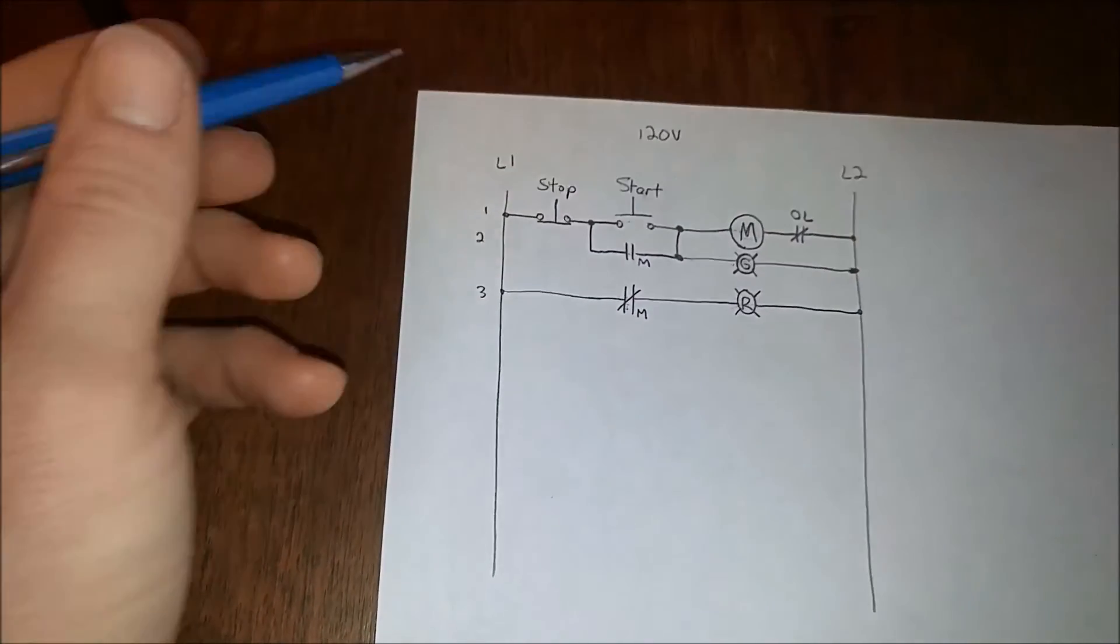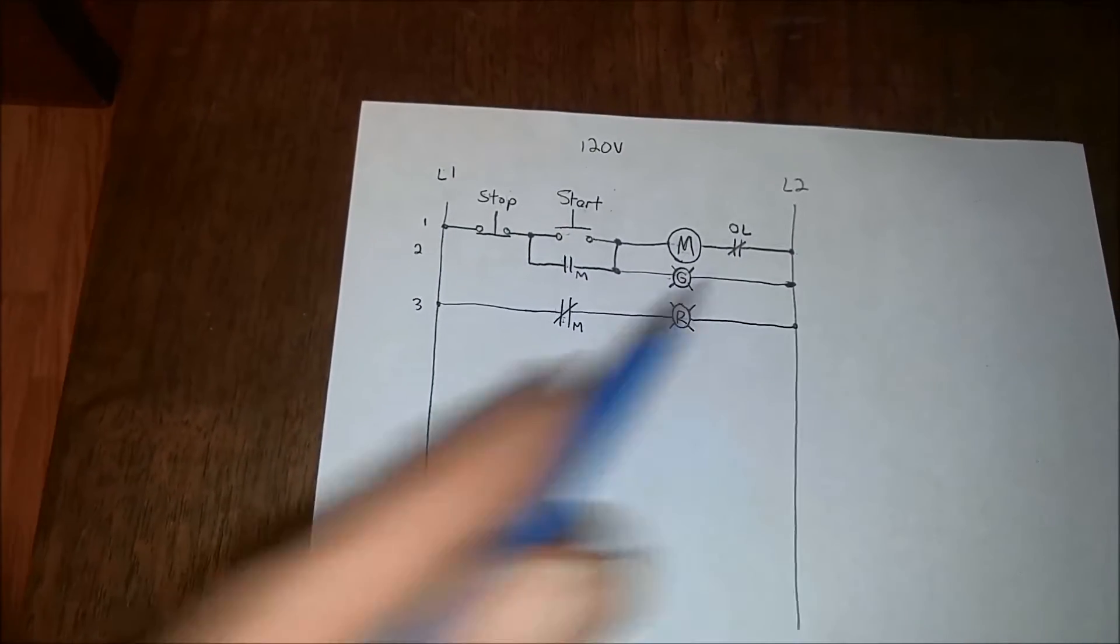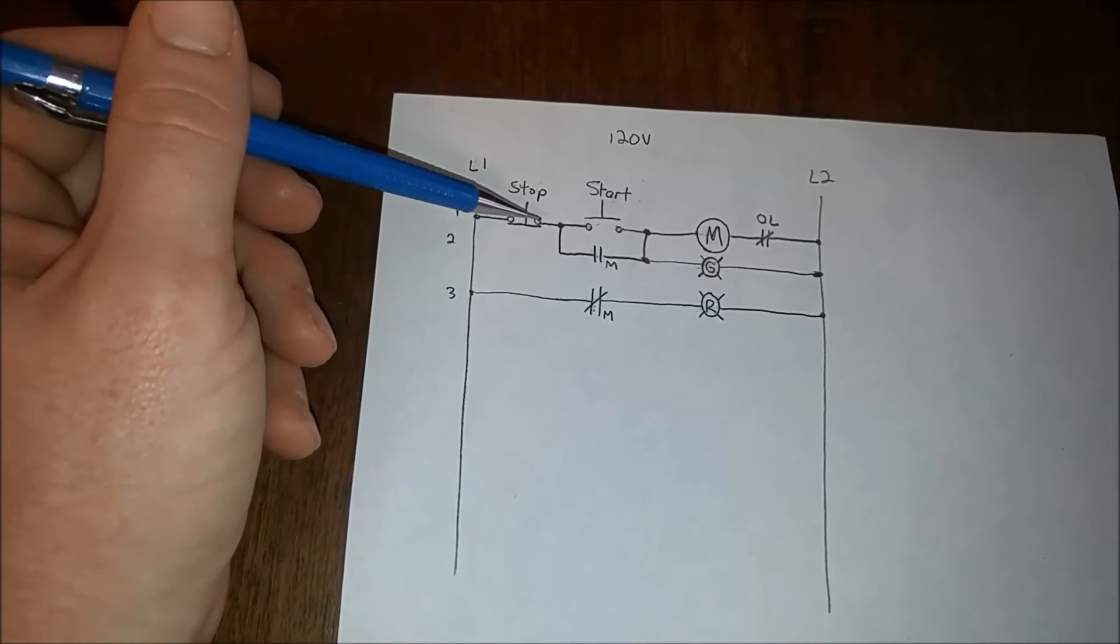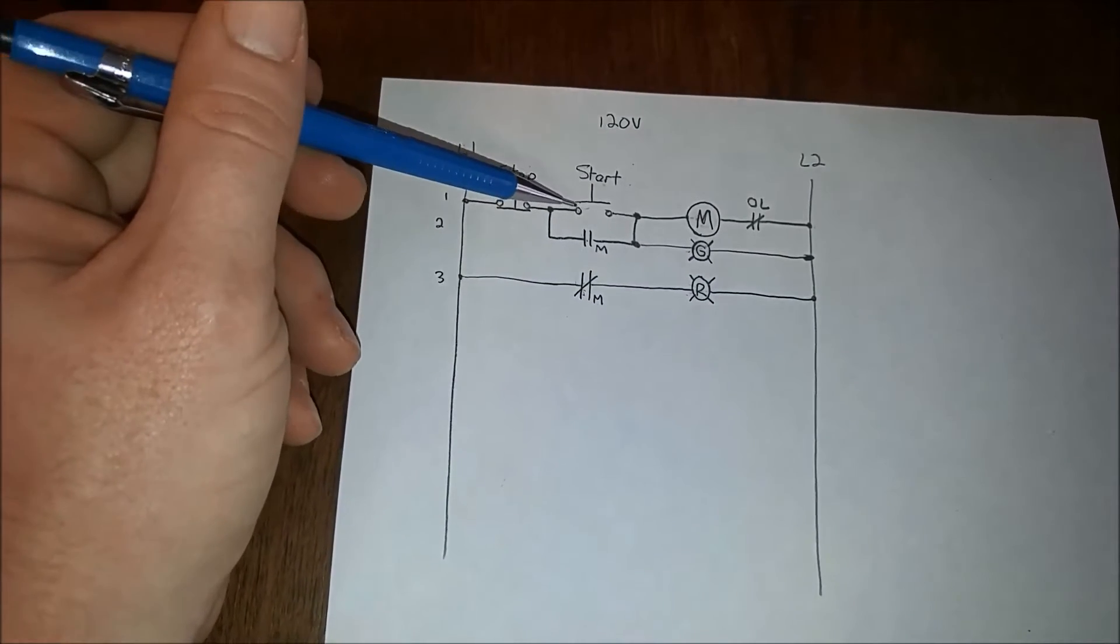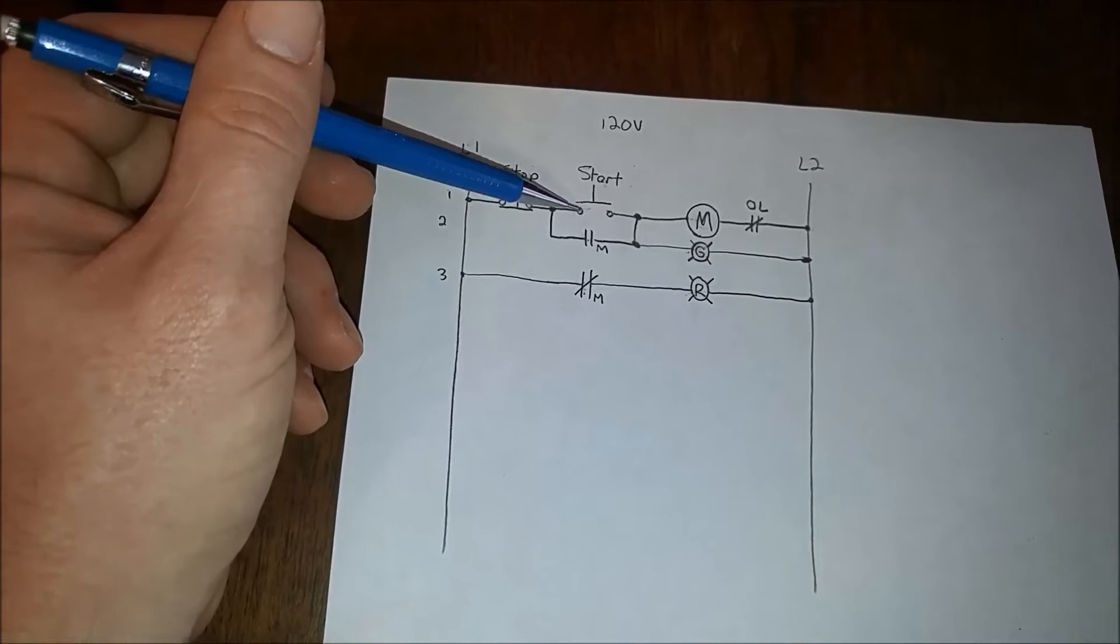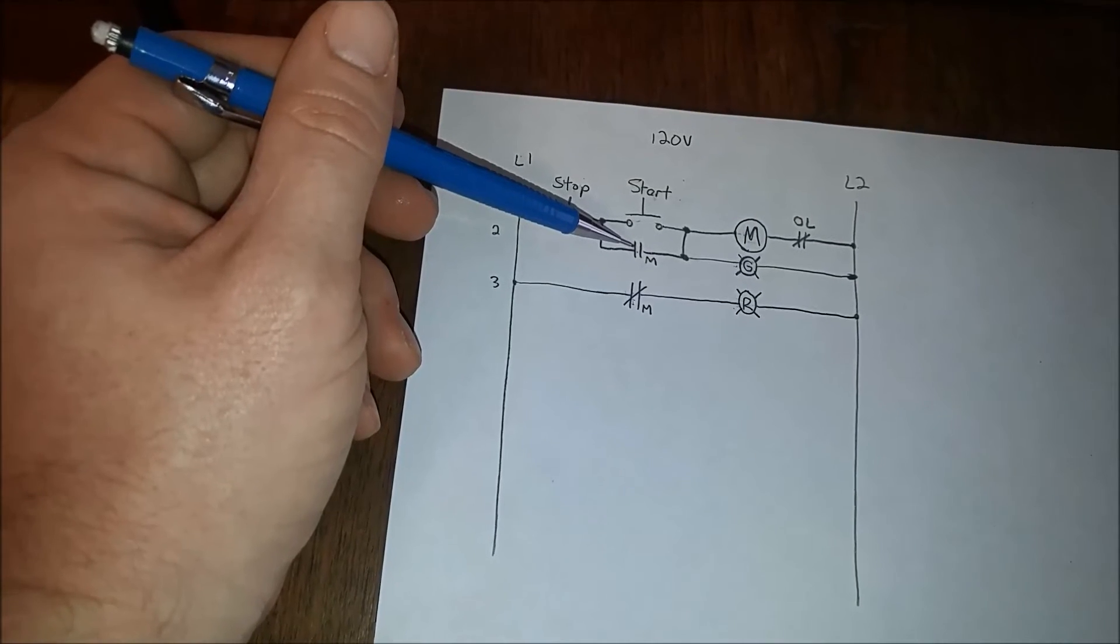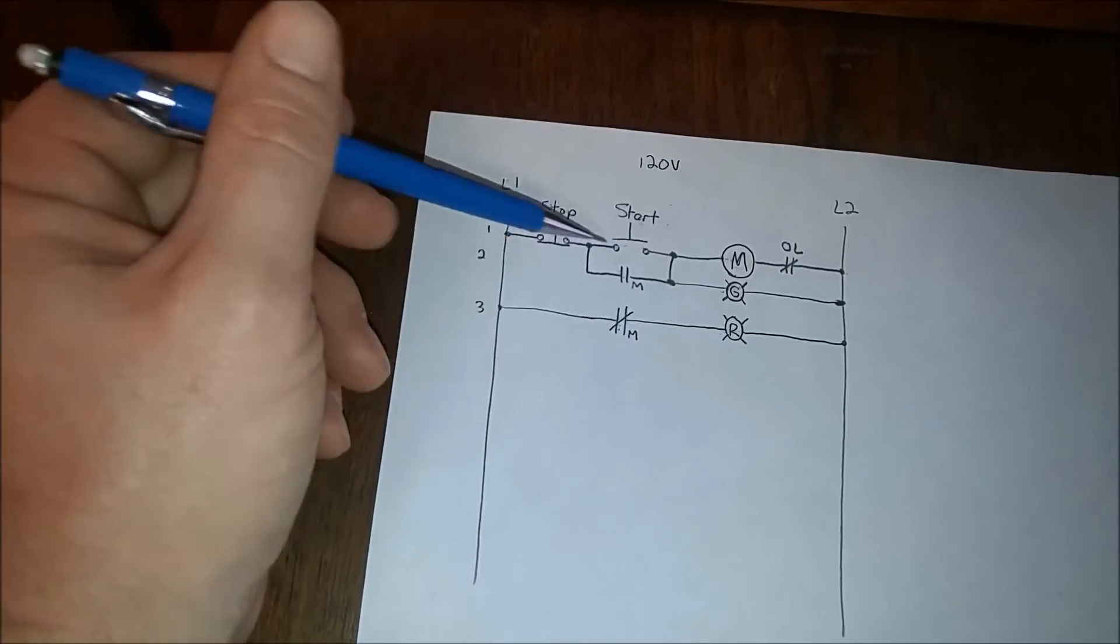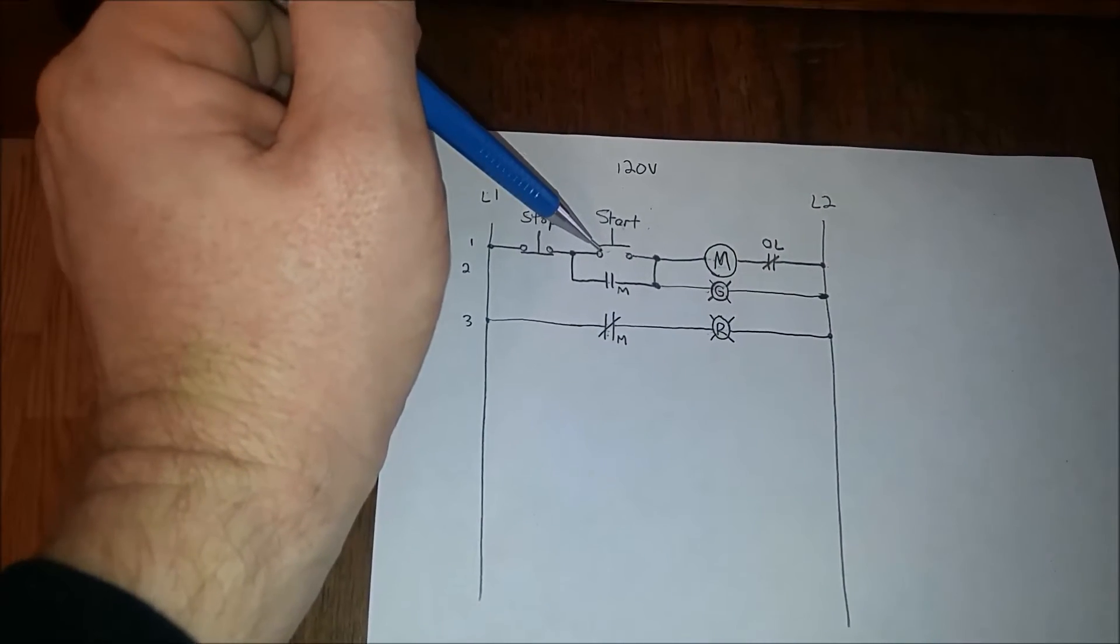The way the circuit works is L1 is your hot and L2 is your neutral. Power comes in here, goes across the normally closed switch, which normally closed means it always conducts. It goes to a normally open start switch which only conducts when you press it down, and that's a normally open auxiliary contact which only conducts when the coil is energized. The power comes through here when you push the button.